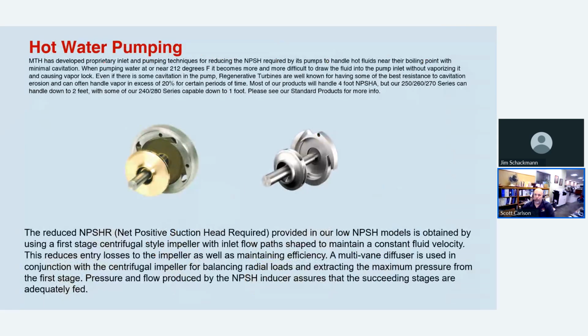If you run into a situation where you have extremely hot water, you can always add a Francis vane style impeller to the front of our multi-stage regen turbines, and what that does is it can knock the NPSH, that's the net positive suction head, required down to as low as 2 feet on certain models, and some of them can even go down to just 1 foot.